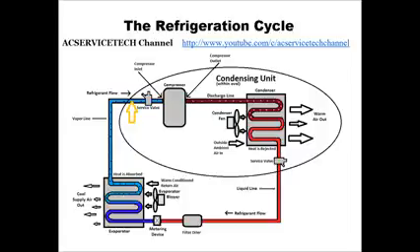If you took it from the middle of the evaporator coil, right after the saturated state where it turns into a complete vapor, the temperature increase from there all the way over to the service valve next to the compressor is called the total superheat. After that it just enters back into the compressor as a low pressure, low temperature vapor refrigerant, and the refrigerant cycle starts all over again.